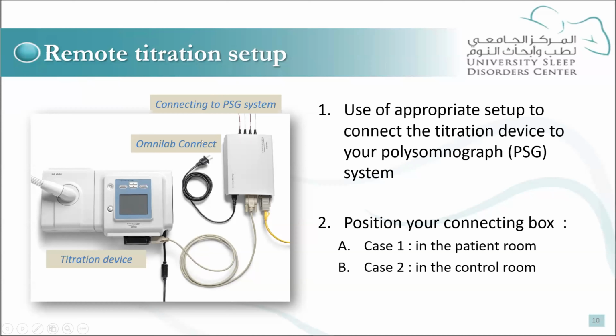So, in this case, from the technical point of view, what you need is what we call a connecting box. In this example, we're using the OmniLab Connect, which is the white box that you see here. This is the box that you use to connect your titration device to your polysomnography or control room. And there are two cases from the technical point of view. Case one is when the box is placed in the patient room, and case two is when the box is placed in the control room.